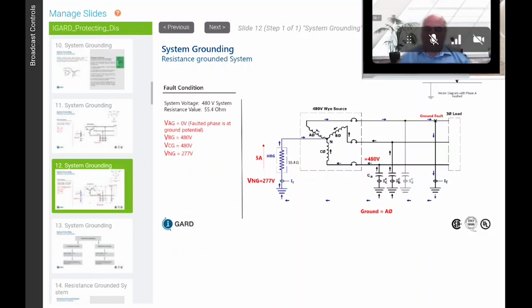So what happens when we have a ground fault on a resistance grounded system? We've now turned A phase and ground to the same potential. We've limited that fault current to 5 amps. B phase to ground and C phase to ground are 480 volts. So as far as a load is concerned, you're still seeing 480 volts phase to phase. Between A and B, B and C, C and A, you have 480 volts. So your load continues to work. All the motors continue to work, your air conditioners continue to work, everything in your facility continues to work. But what we've done is we limited that fault current to 5 amps.